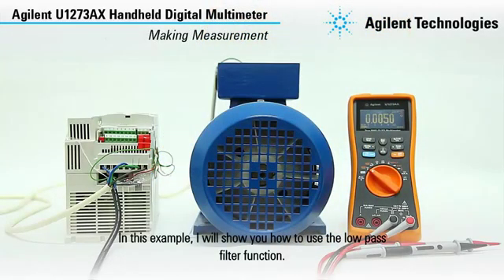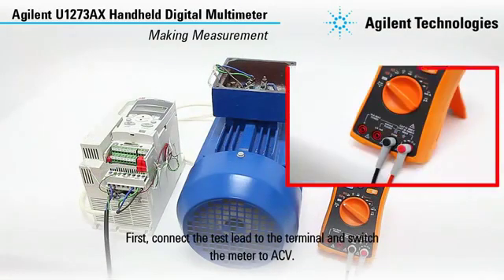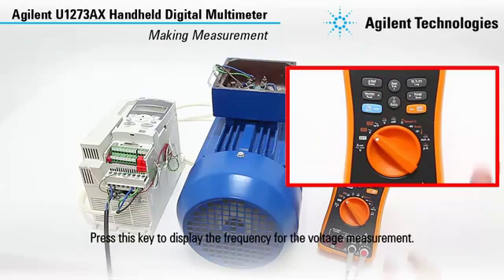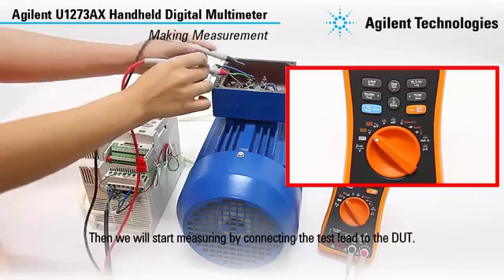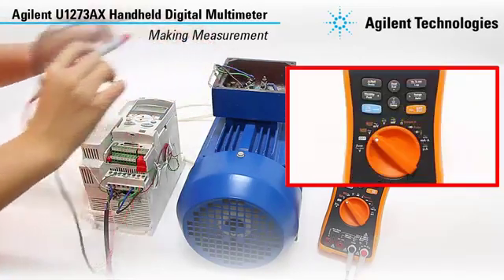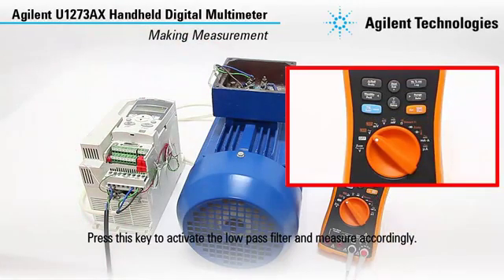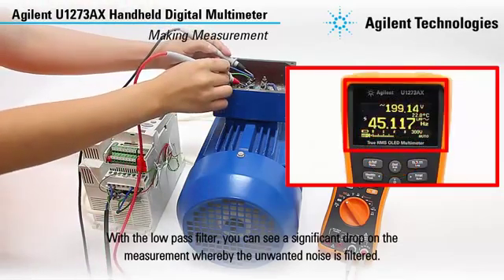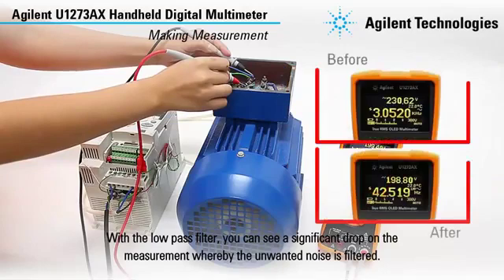In this example, I will show you how to use the low-pass filter function. First, connect the test lead to the terminal and switch the meter to ACV. Press this key to display the frequency for the voltage measurement. Then we will start measuring by connecting the test lead to the DUT. Press this key to activate the low-pass filter and measure accordingly. With the low-pass filter, you can see a significant drop on the measurement whereby the unwanted noise is filtered.